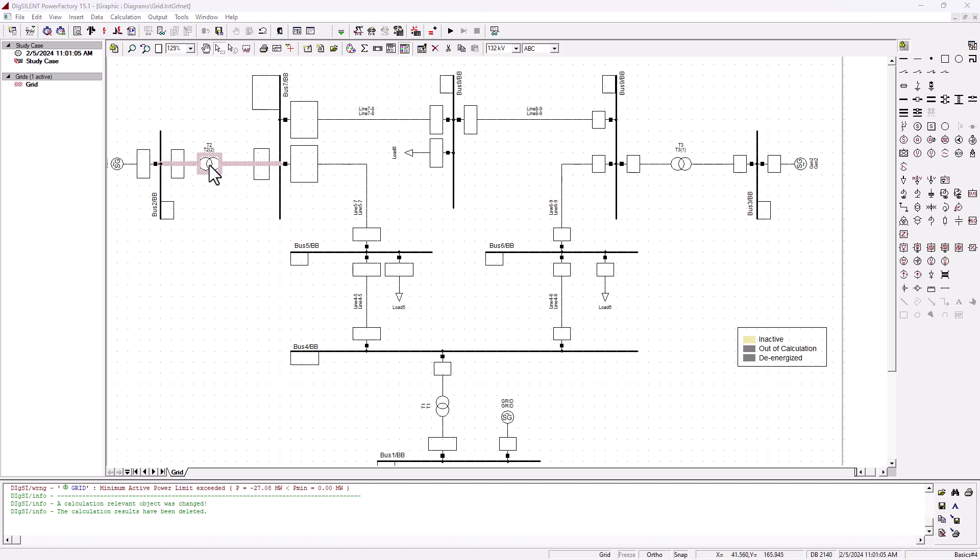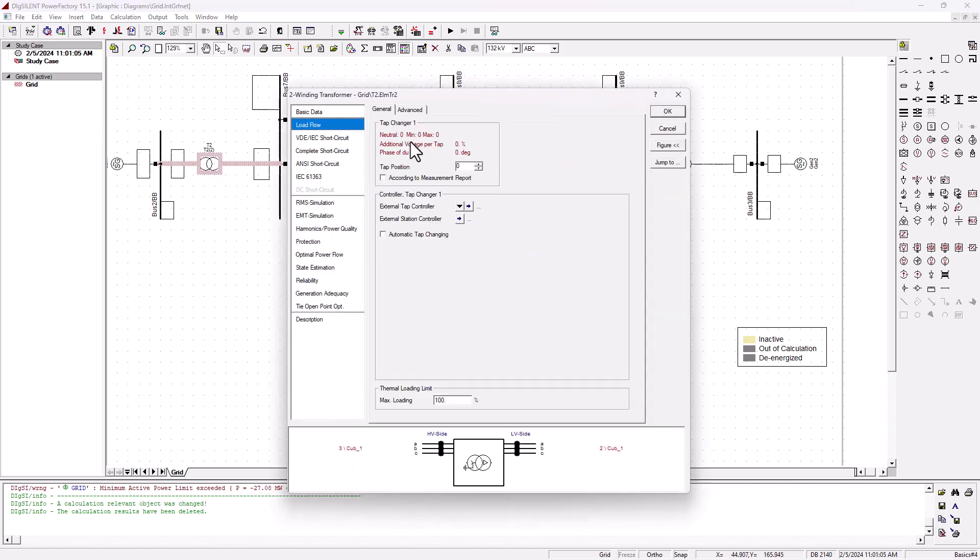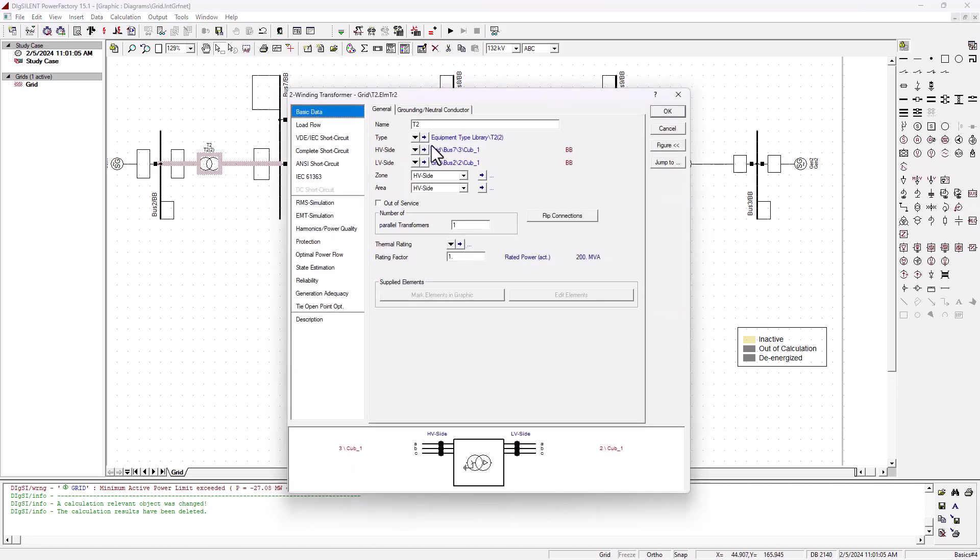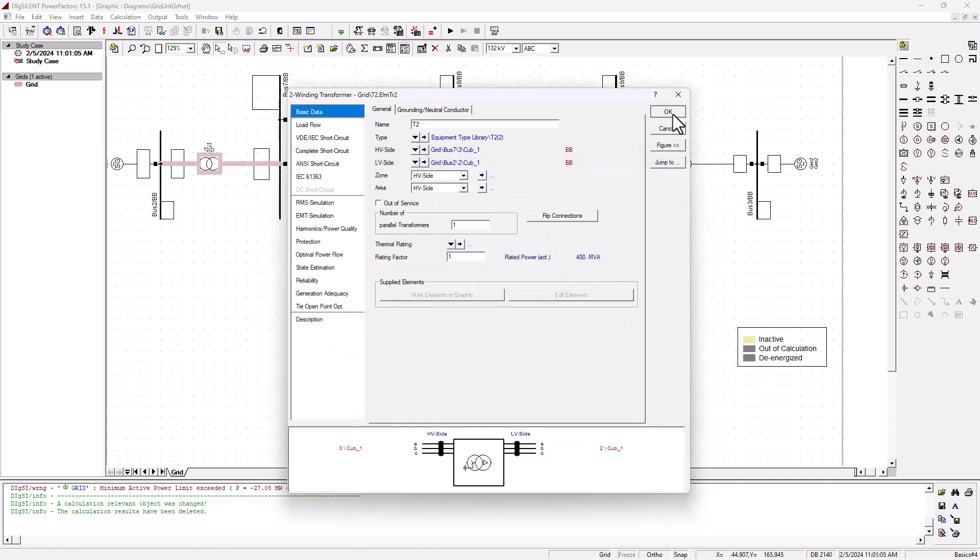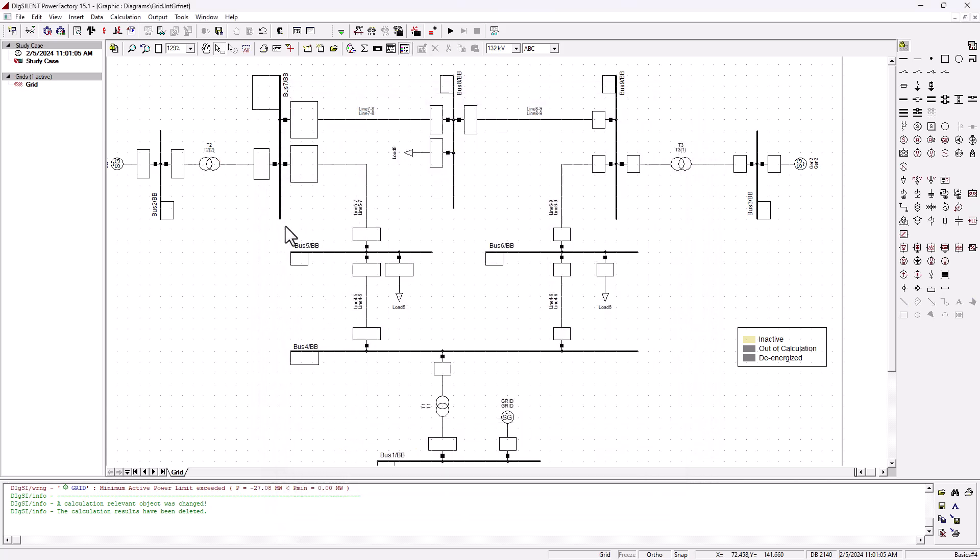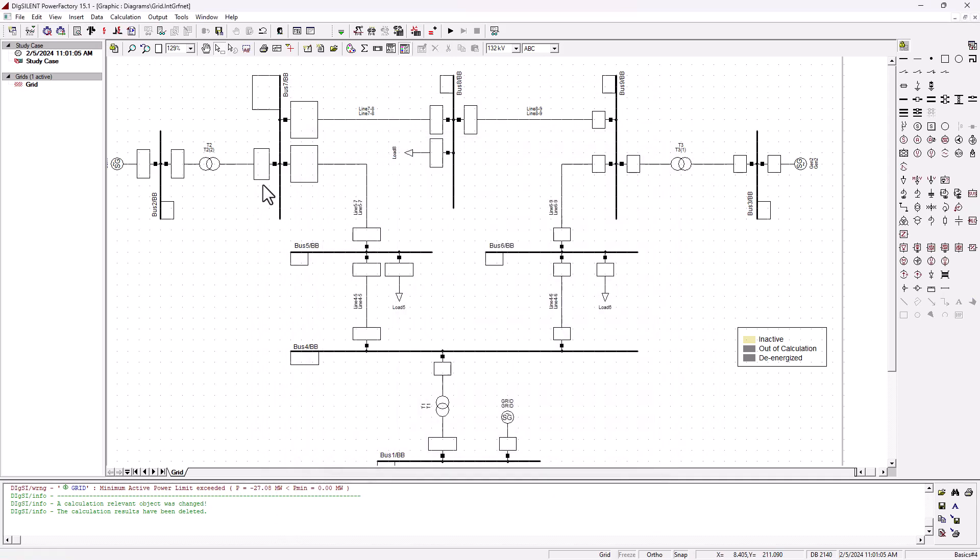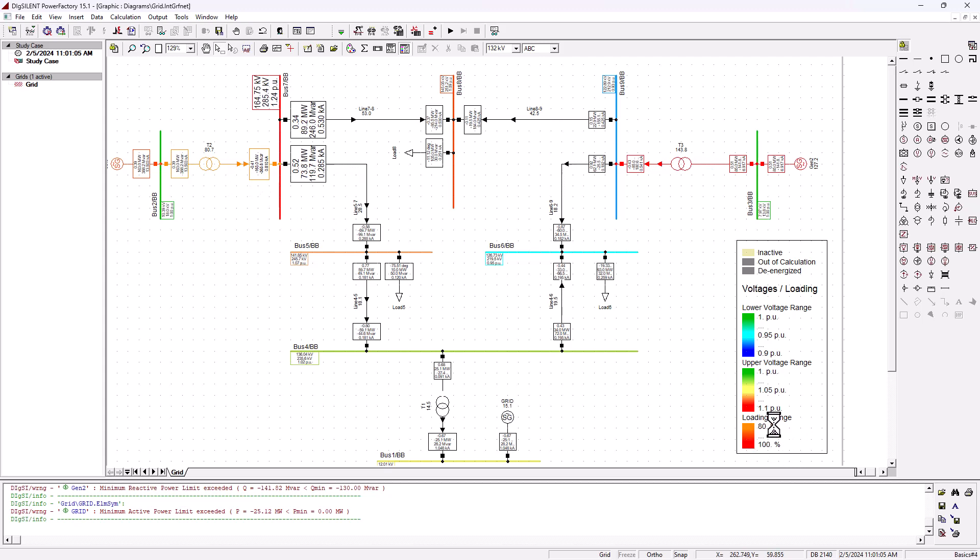You must also increase the size of your transformer. These are just what you can do in the immediate. Let's say we put this also 400 MVA. Then you run the load flow analysis again. Now you can see that the loading here changes. You're no longer onto the red zone.